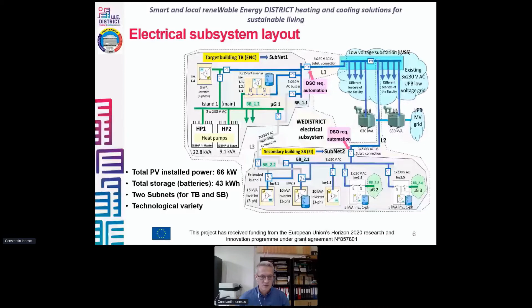One important section of our demo is the system control and automation. There is a central equipment, the main PLC, which collects all data from the thermal subsystem equipment. The PLC is also responsible for receiving set points from the in-house developed SCADA EMS system and sending these set points to the subsidiary control equipment. The overall concept allows integration of the thermal system into the overall SCADA EMS system of the WEDISTRICT project, and to communicate on different levels, locally and remotely.